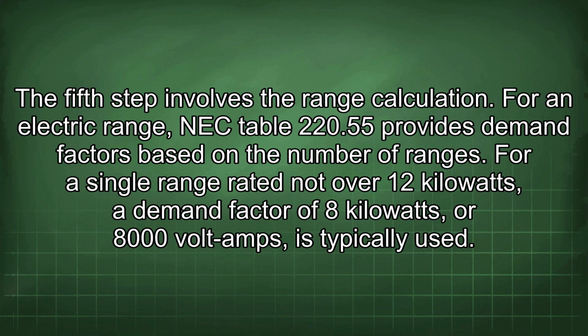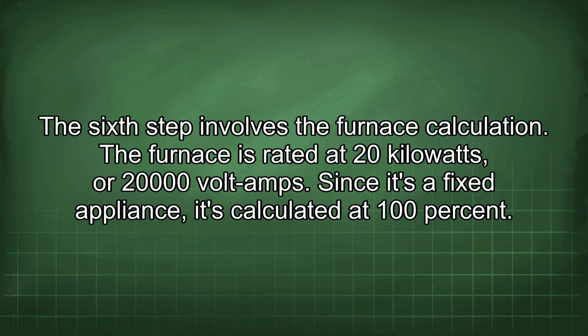The fifth step involves the range calculation. For an electric range, NEC Table 220.55 provides demand factors based on the number of ranges. For a single range rated not over 12 kilowatts, a demand factor of 8 kilowatts or 8,000 volt amps is typically used. The sixth step involves the furnace calculation. The furnace is rated at 20 kilowatts or 20,000 volt amps. Since it's a fixed appliance, it's calculated at 100%.